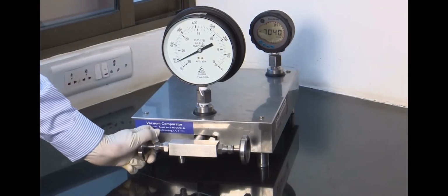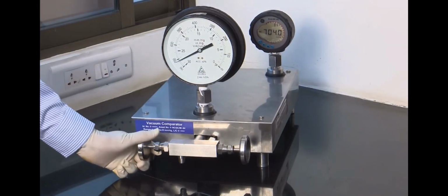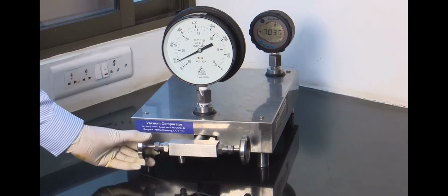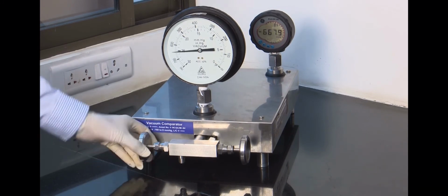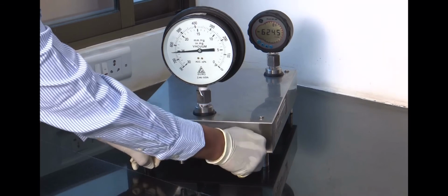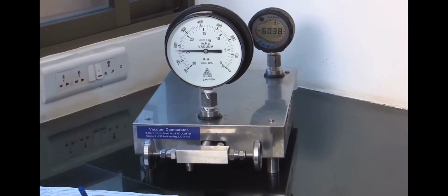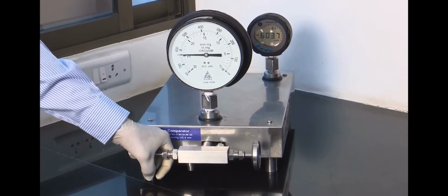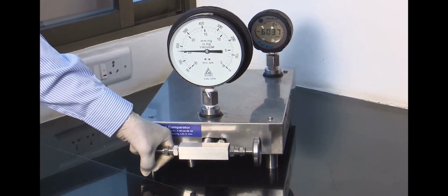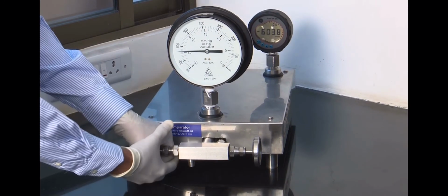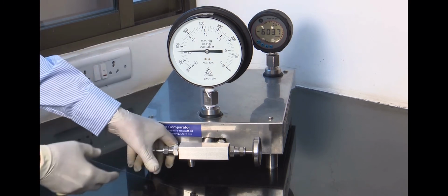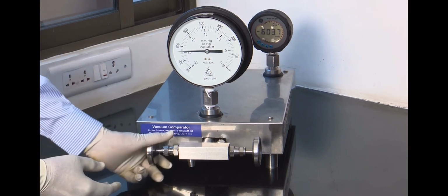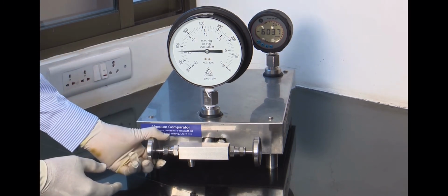Similarly, I am performing -630 mm Hg calibration point for decreasing cycle. Allow it to stabilize for 30 seconds. Now record the reference standard reading in the worksheet. In this way, the demonstration of calibration of vacuum gauge for 2 points is completed for this training purpose. You have to do this for all the points as per the method.